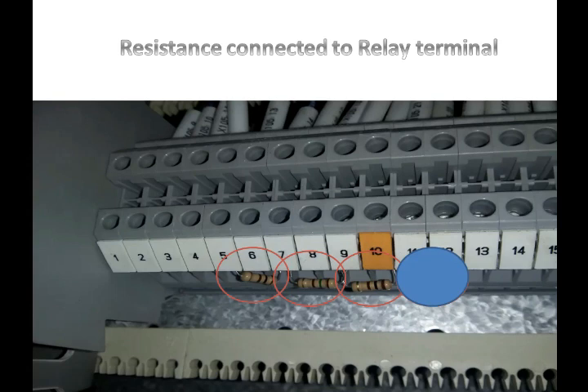First, I connected 145 ohms for U, 145 ohms for V, and 150 ohms for W winding. I have connected all the resistors corresponding to the TB number as per the schematic diagram.